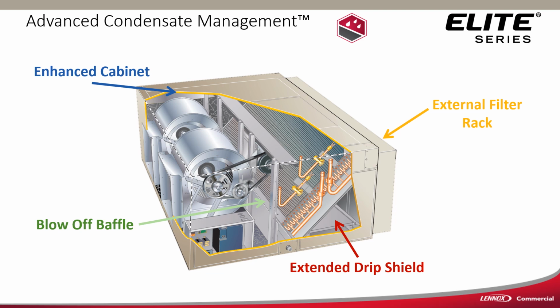As we look at the ELA air handler a little closer, enhanced cabinet insulation to increase our insulation levels. It's got again the external filter rack that will take up to a 4-inch filter. If you look at the bottom where it says extended drip shield, for those low static applications, if water starts coming off of the return side of the coil, it's collected in that drip shield, and that just runs it right into the drain pan. On the leaving air side of the coil, we have a blow-off baffle, on high static applications, to help prevent water condensation from being introduced to the blower motors.